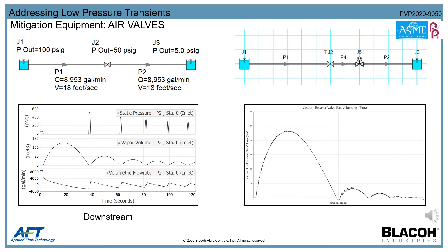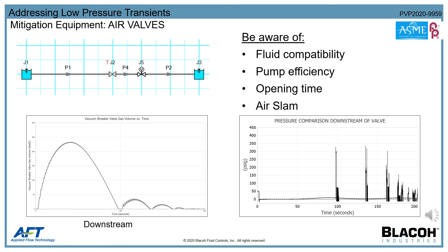Moving on to mitigation equipment, beginning with air vacuum valves. When a system experiences a significant dip in pressure leading to cavitation, one method of mitigation is an air vacuum and release valve that opens the system to atmosphere, drawing in air to allow the system to equalize. For some systems, this is all the mitigation needed. However, the first challenge to be aware of is fluid compatibility — drawing air into a highly combustible hydrocarbon application is extremely dangerous, and another closed-type surge mitigation device should be considered.